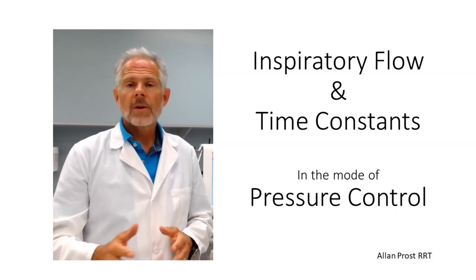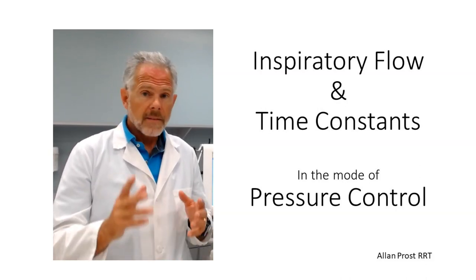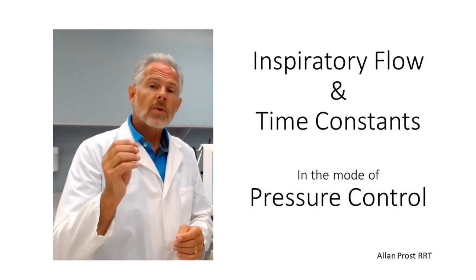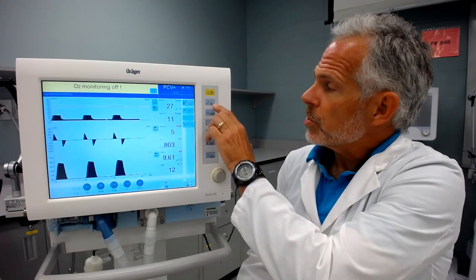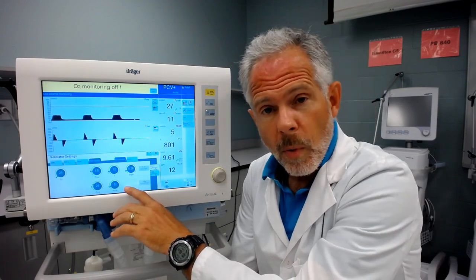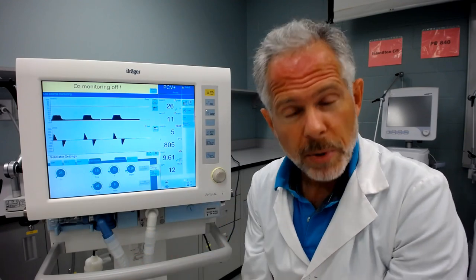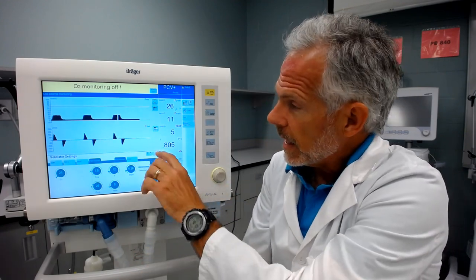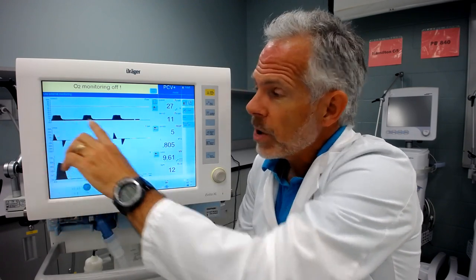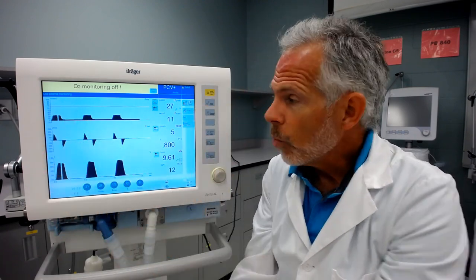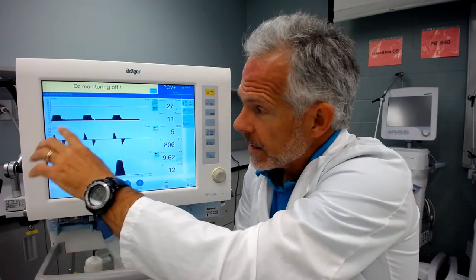My name is Allan Prost and I'm going to do a demonstration today on the effects of ventilator controls on inspiratory flow in the mode of pressure control. In pressure control, we set up a pressure gradient between the PEEP or base airway pressure and the peak inspiratory pressure. That pressure gradient inflates the lungs to a specific pressure, resulting in a certain tidal volume delivery and creating inspiratory flow, which is what we're examining today.